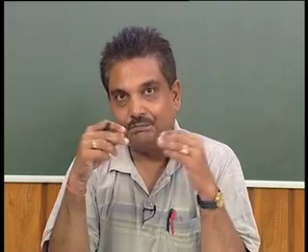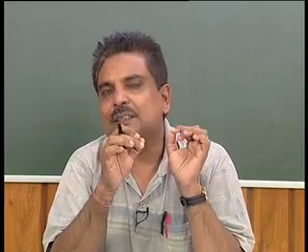What are these? HSI is the heat transfer coefficient for the scale on the inside surface of the inner pipe. It is expressed as an equivalent heat transfer coefficient because, though the scale is a solid material and the resistance could be written in terms of thickness, it is difficult to measure the thickness of the scales, which is a very fine amount.